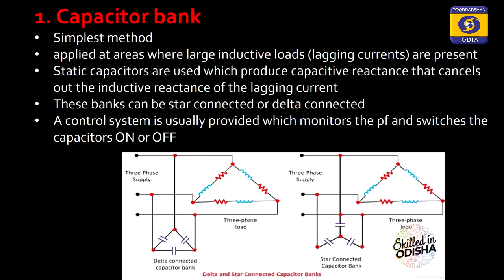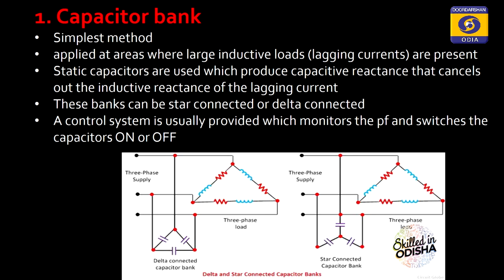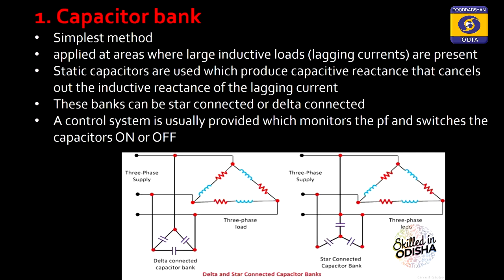The simplest equipment is a capacitor bank — a static capacitor. It is connected in parallel with the load and injects leading current into the power system so that the lagging power factor is stabilized. For a three-phase load, it is connected in star or delta configuration. Advantages include being lightweight and easy to install.